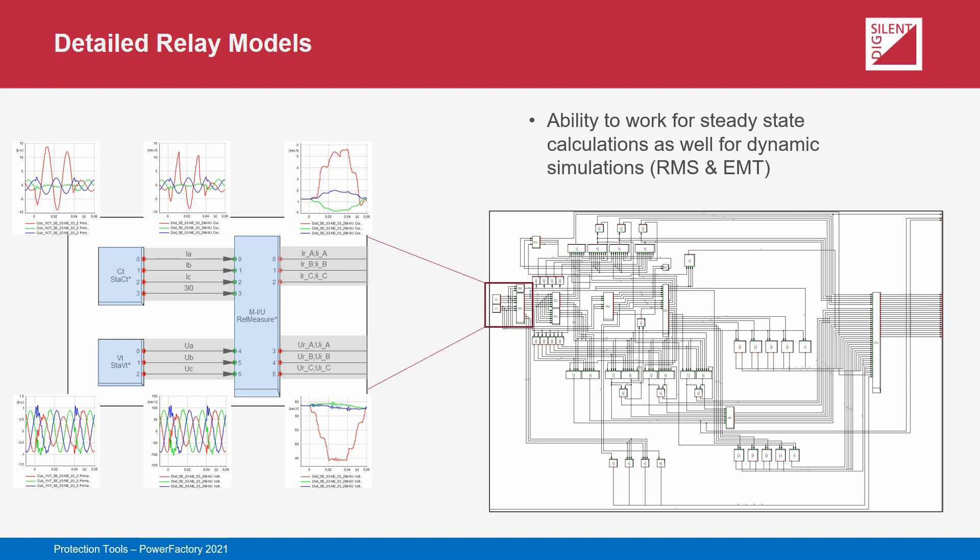For each block, the model class it represents has a set of signal names, with each signal having a specific definition. These definitions are detailed in a set of technical reference documents which are available within the software for each model class. Users can configure the measurement block according to their application. For example, the 1A or 5A current rating of the relay can be specified, as well as the sampling method. For blocks such as the time overcurrent block, settings such as the current threshold and time dial or time delay can be specified along with the used time overcurrent characteristic.